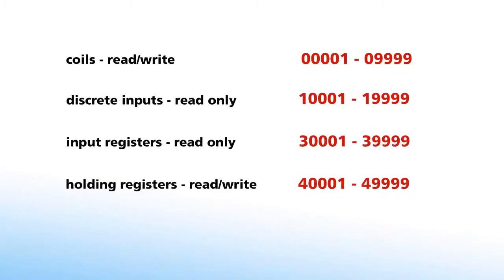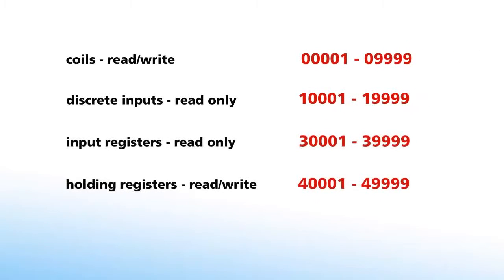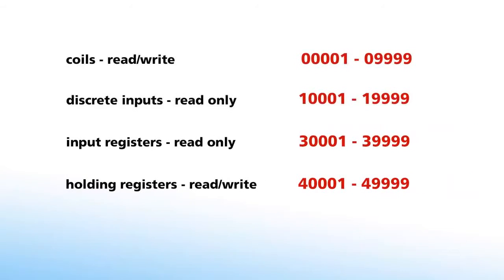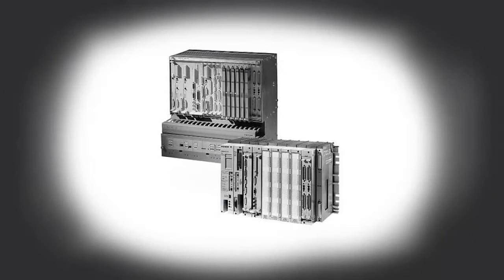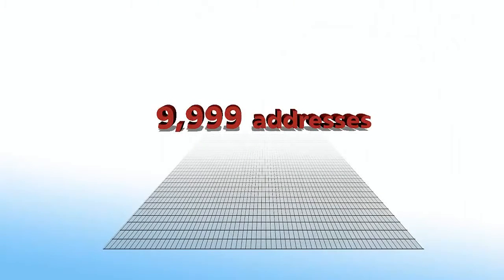Now let's talk about Modbus's eccentric addressing system and the different data tables. There are four tables where information is stored. Two tables store simple discrete values called coils, and two store numerical 16-bit values known as registers. For each type of data, there is one read-only table and one read-write table. There are no tables for 32-bit data types because back when Modbus was defined, double integers and floating point values were not available in PLCs. There is a way to use those data types though, and we'll get to that in a moment. Each table has a maximum of 9,999 addresses.